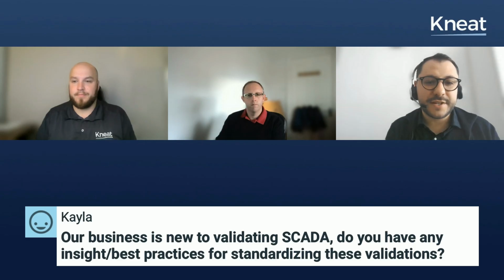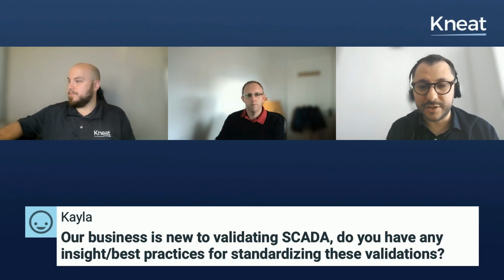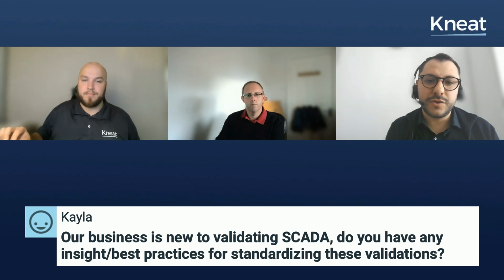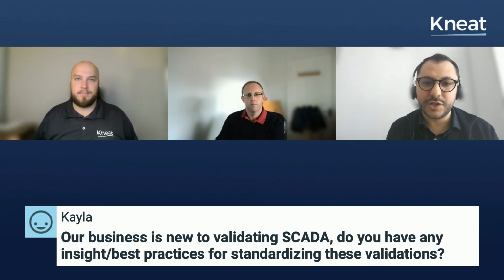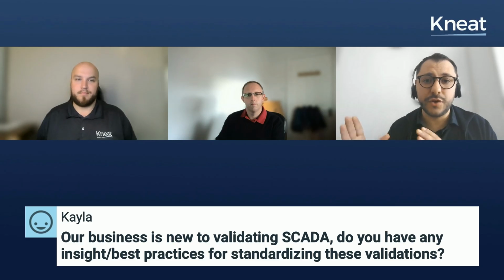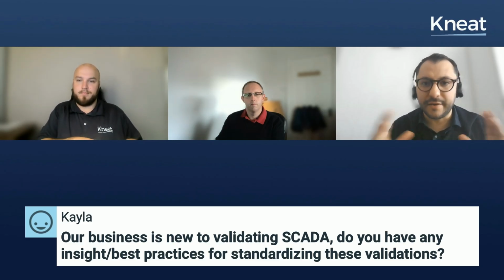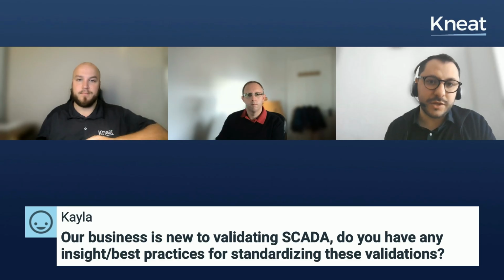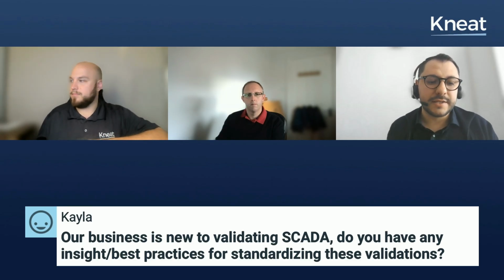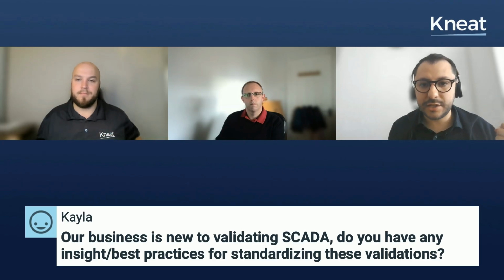Yeah, absolutely. The first best practice is to include all the data integrity requirements, but the focus during the SCADA validation is the risk assessment, because it's important to define the critical elements of your process in the risk assessment, and focus your validation effort in accordance with these critical elements. So you don't need to validate everything, but validate in accordance with your critical elements and in accordance with your risk assessment. So the effort is related in accordance with the data integrity requirements and the critical elements of your process to validate your system.